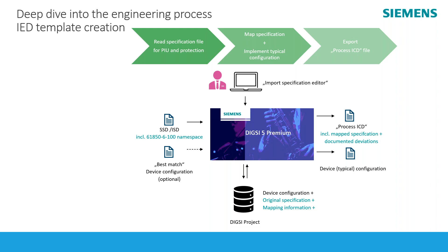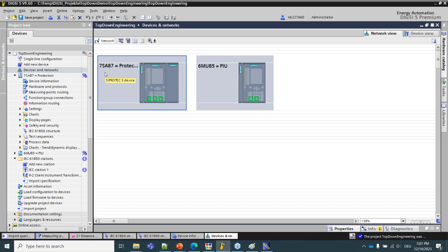To show that, I will jump to the DIGSI software. The DIGSI software is our IED configuration tool used to configure all SIPROTEC 5 devices. In this case, our 6MU device, a merging unit, as well as the 7SA87, which is the distance protection device commonly used at Elia.